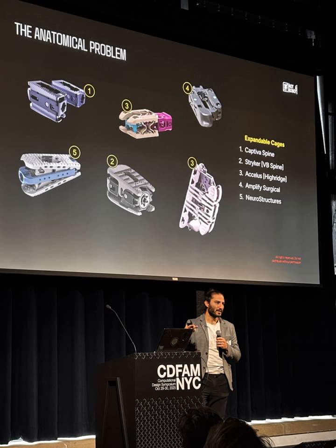So what have we tried to do as engineers to solve the problem? Well, these expandable devices are kind of a stopgap to say, we don't know what is going to happen in the anatomy. Yeah, we've got some imaging techniques, we can kind of tell what's going to happen. So we want to create devices that go into the body and can then be adjusted in situ, which has been honestly really cool. The ability to go in and say, we don't quite know how this is going to fit, so jack up the spacer inferior-superiorly, medial-laterally, anterior-posterior. The problem is a lot of these devices are finicky, they're expensive, and at the end of the day, you still don't get a perfectly conformal fit.